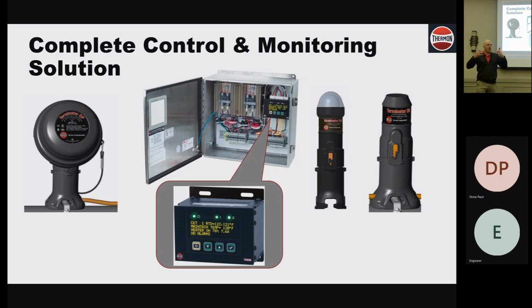So we have control schemes that, number 1, are smart. You can talk about energizing the cable at programmed intervals, pulling an amp draw, putting that into a trend line, and then looking at that trend line over time and making certain the health of your system is appropriate. We have SCADA integration where it can bring smart alarms back into a control room. We can integrate that with Power BI and a Microsoft SQL server, so you can have reports that are logical and easy to understand as opposed to just an alarm light. These are all differentiators that truly are helping power plants across the country operate more efficiently.